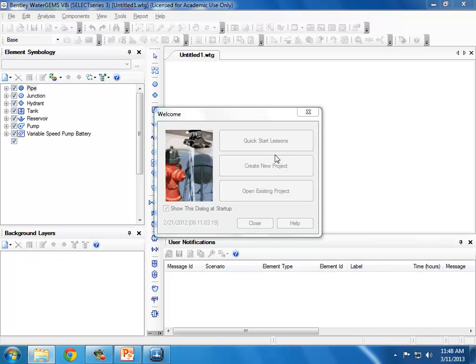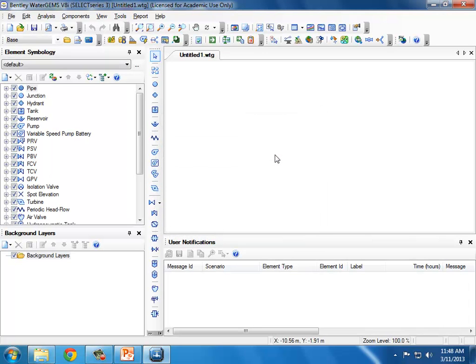While it's loading up, let me just mention that the main thing of these maps is to show that you've optimized the network, that the pipes are as small as they can be without being too small. And too small means that under maximum demand flow the pressure is below 240. And so under maximum demand flow, if your map has lots of junctions that are still in the 500, 600 range and none of them that go down below 300, then that's an indicator that probably you could make certain pipes smaller than they are right now.